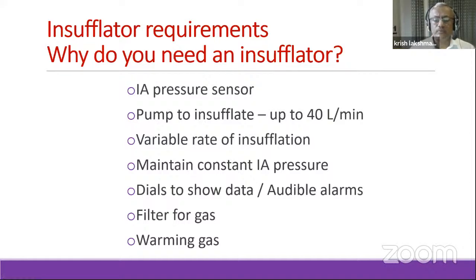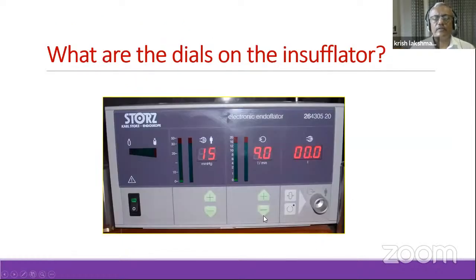From time to time, you must be looking at it. If you find that the pressure is going up, you must have an alarm. You can have a filter for the gas. Doing it just by hand, you won't have a filter. You can warm the gas. So these are the advantages of an insufflator.